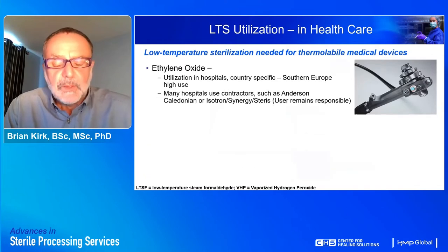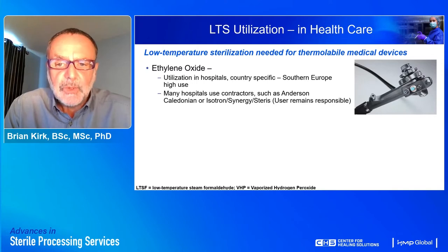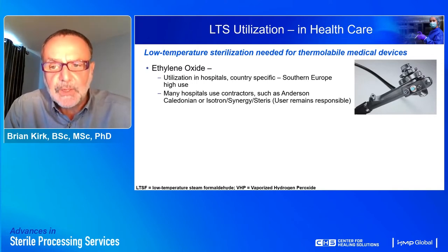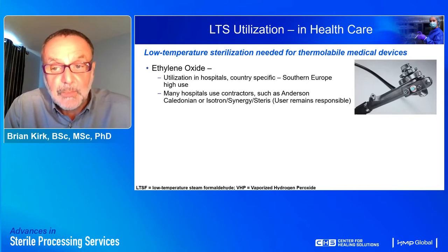Looking at the utilization of low temperature sterilization in healthcare: ethylene oxide is a very reliable technology with wide application, but its use is country specific. It's widely used in the medical device industry on a large scale to sterilize pallet loads of single-use, usually plastic-made medical devices.